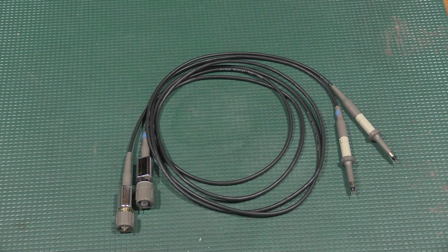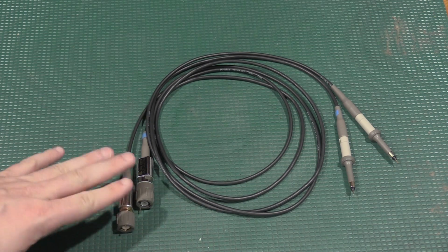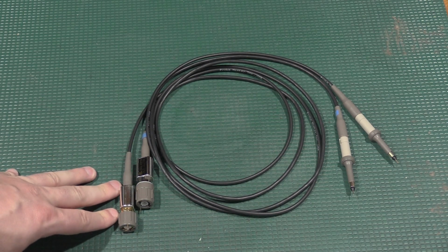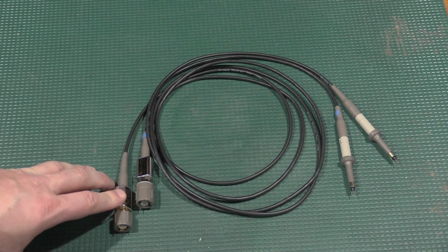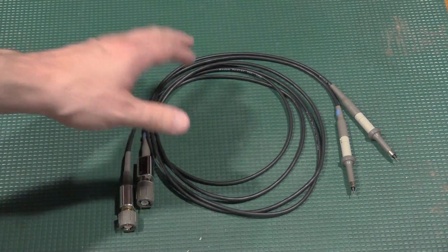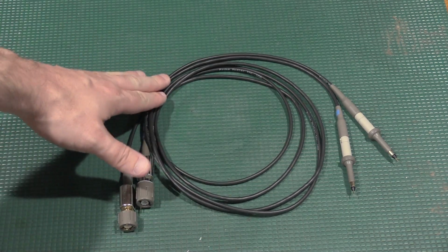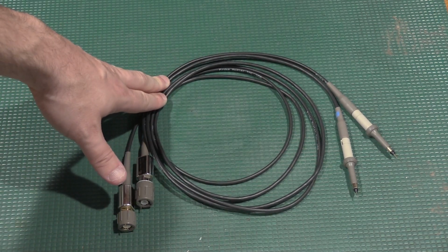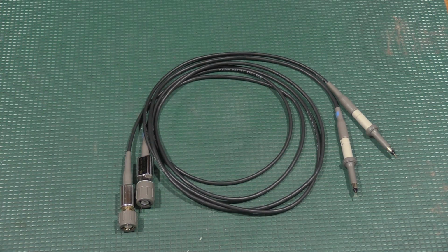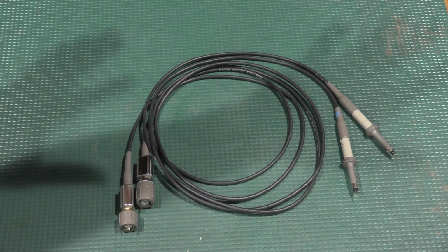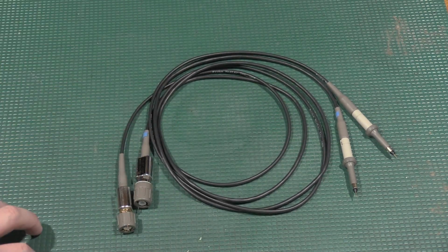As you go up in frequency, they derate voltage-wise very fast. So make sure you check the charts and the curves in the data sheet to see what that derating is, because especially as the frequency goes up, the insulation withstanding resistance starts to break down, and you can get buzzed just by touching the cable if the conditions are right. As a very wise person once told me, high voltage is fun, just don't get it on you.